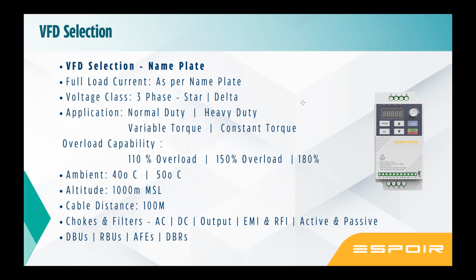Before connecting a DC choke, you need to also check the selection parameters and other aspects. Then comes the output choke. The output choke, as I mentioned, is used where there is a distance issue. Then there are filters, EMI and RFI: electromagnetic interference, radio frequency interference. Then EMC, electromagnetic compatibility. So there are E1, E2, or C1, C2, C3 classes of filters. By default, you get C3 or C4 filters. Now, if your environment is going to have highly sophisticated electronics, you have to have the right kind of EMI filter, class 1, class 2, E1, E2 type of filters. Again, it is built in and sometimes you need to define it.